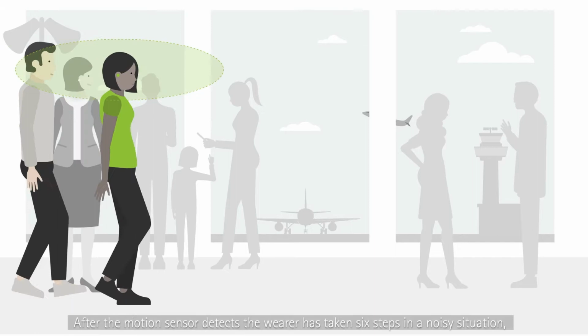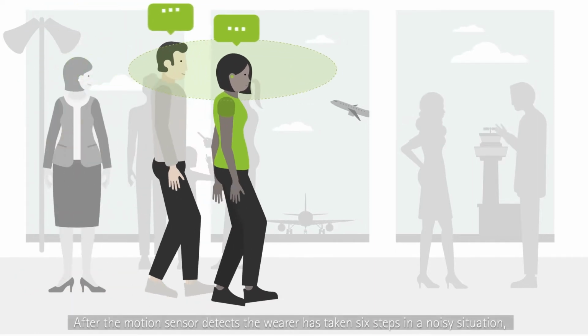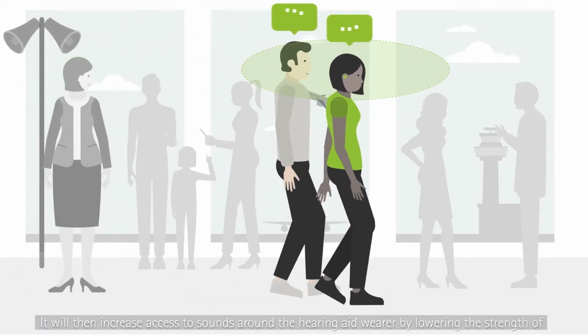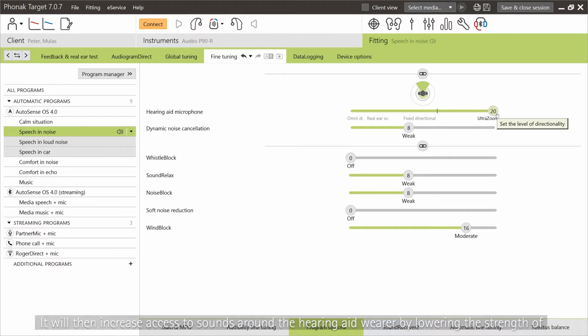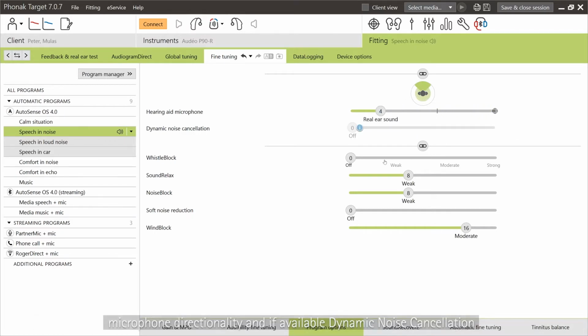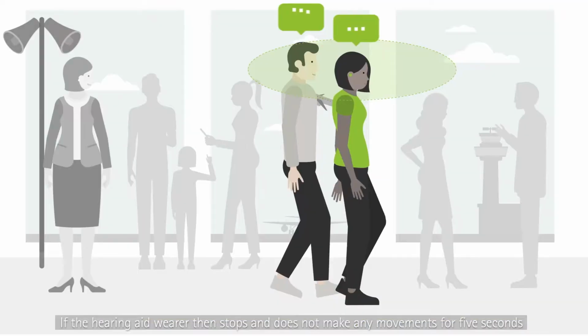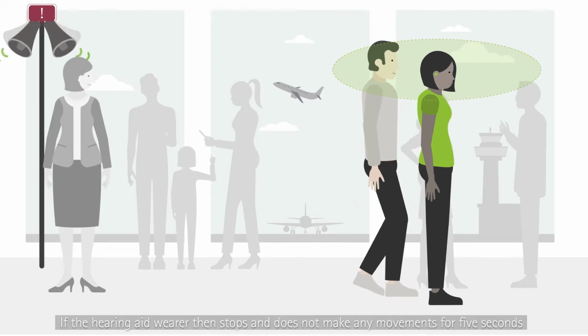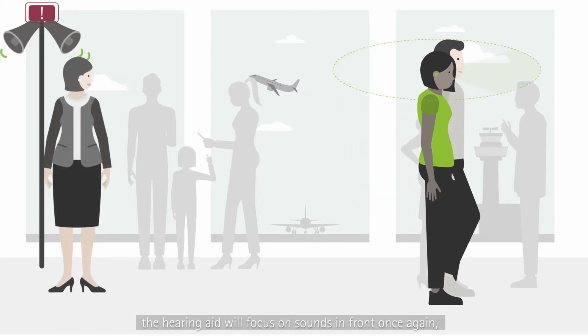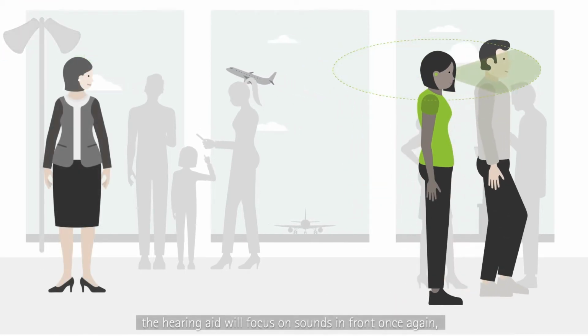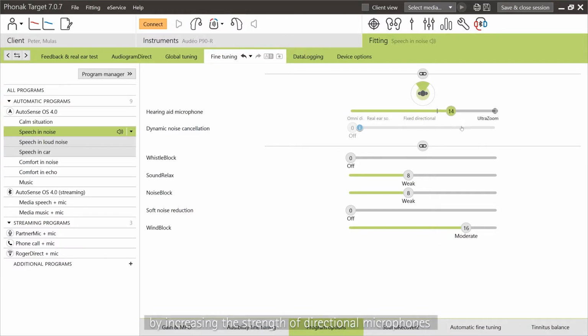After the motion sensor detects the wearer has taken 6 steps in a noisy situation, it will then increase the access to sounds around the hearing aid wearer by lowering the strength of microphone directionality and, if available, dynamic noise cancellation. If the hearing aid wearer then stops and does not make any movements for 5 seconds, the hearing aid will then focus on sounds in front once again by increasing the strength of directional microphones and dynamic noise cancellation if available.